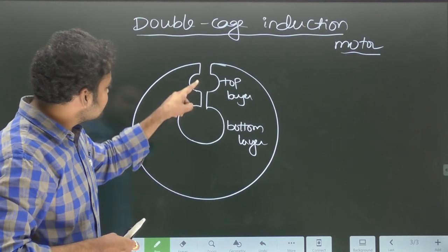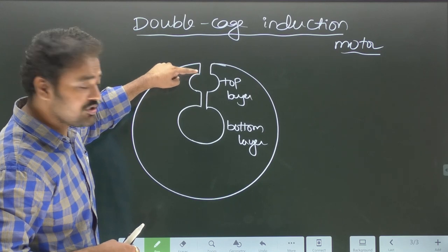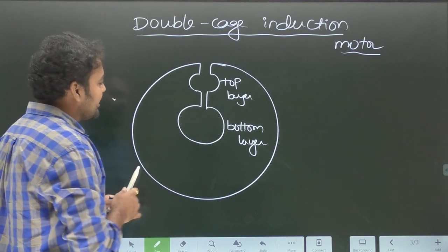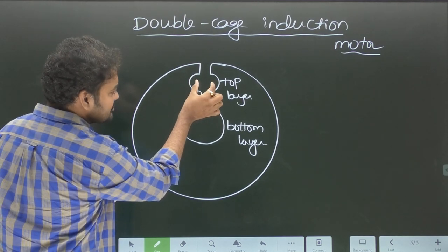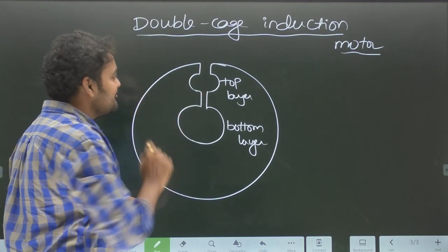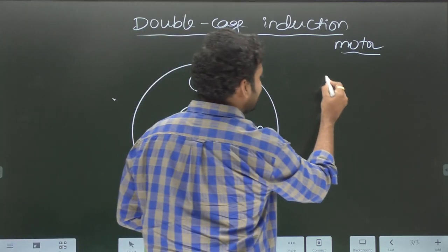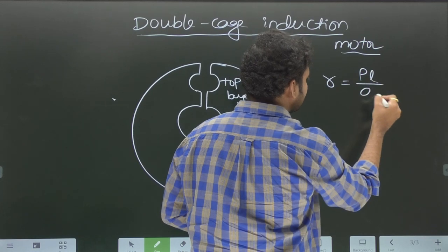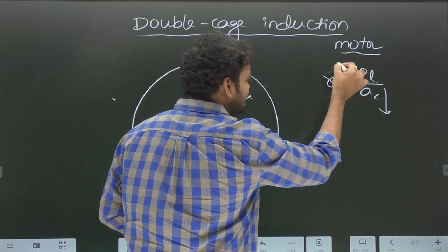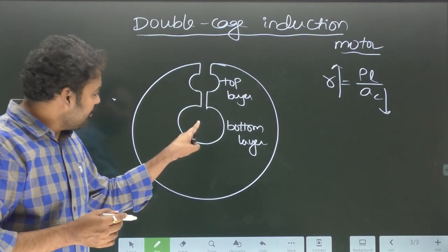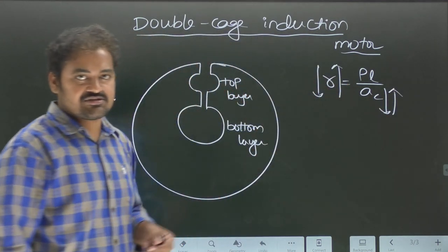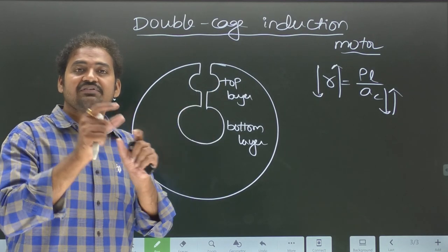The slot consists of two layers — one is the top layer of the rotor and another is the bottom layer. The top layer has less cross-sectional area and the bottom layer has more cross-sectional area. This is to create a resistance difference between the top layer and bottom layer. We know that resistance offered by any conductor is ρL divided by cross-sectional area. So the conductor in the top layer offers higher resistance, and the conductor in the bottom layer offers less resistance.